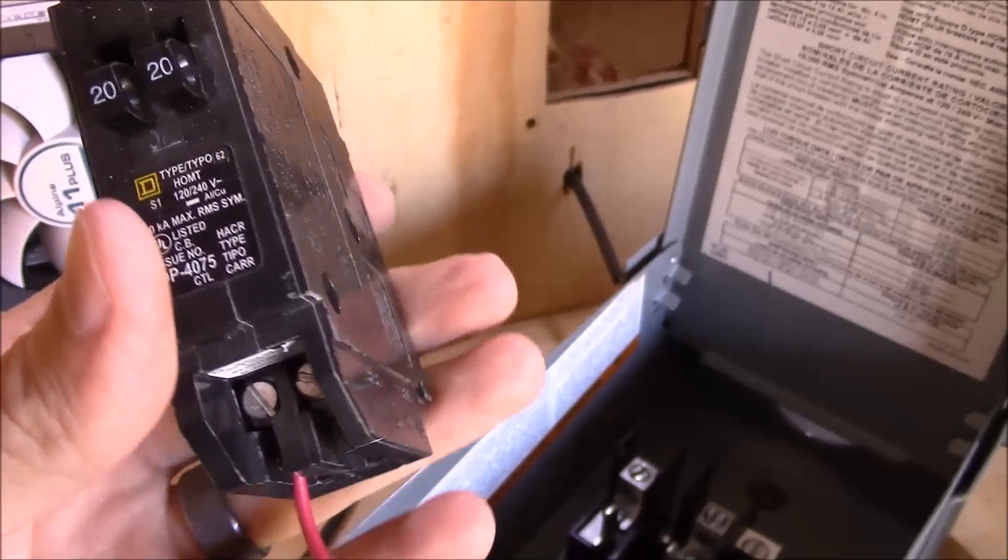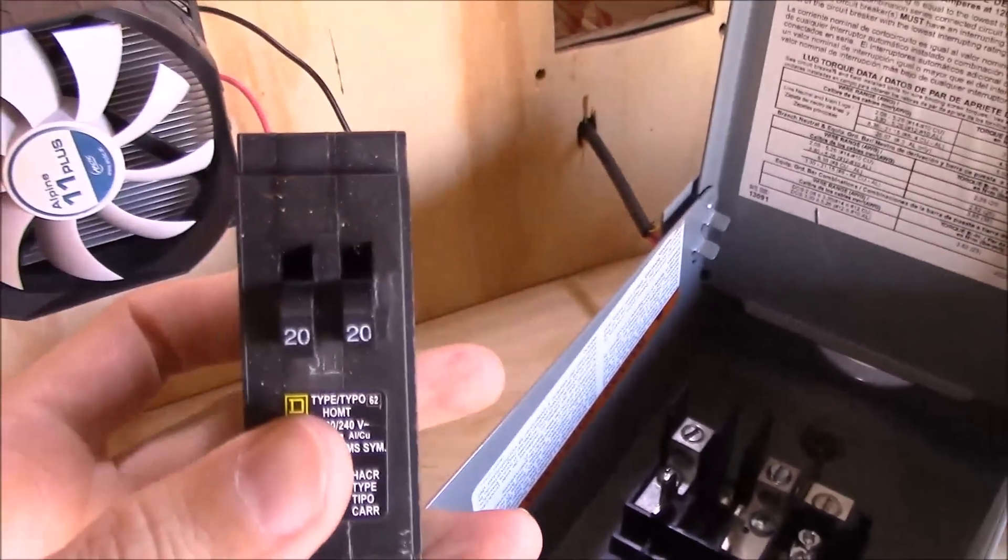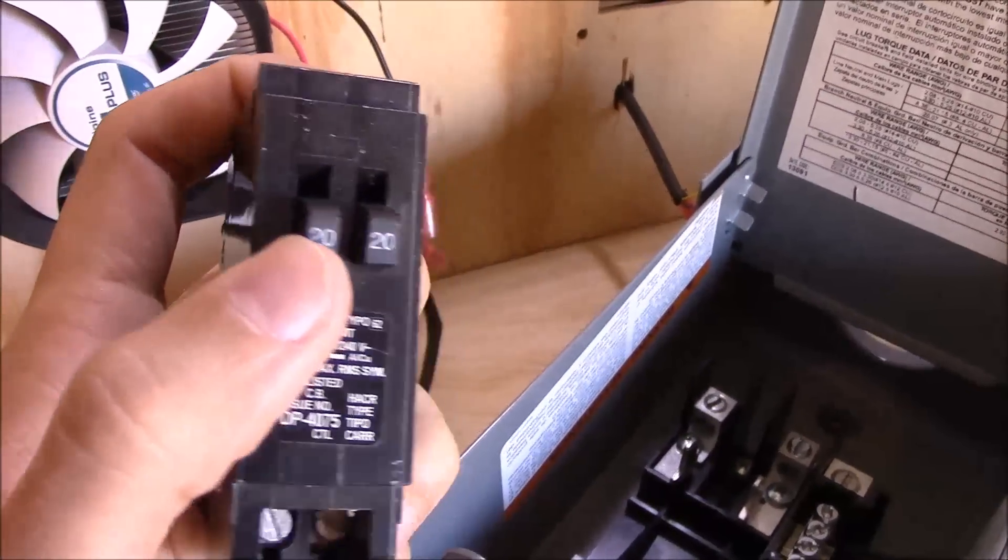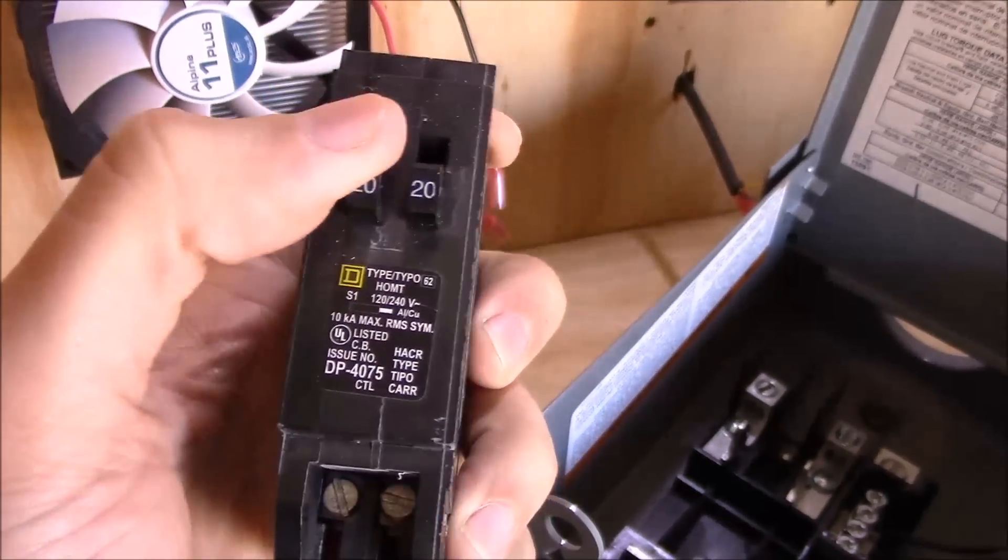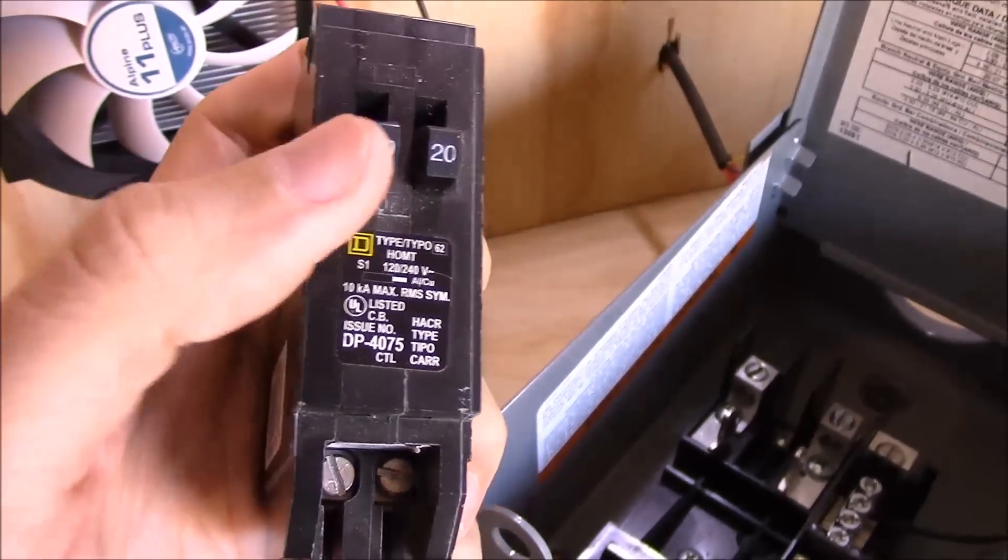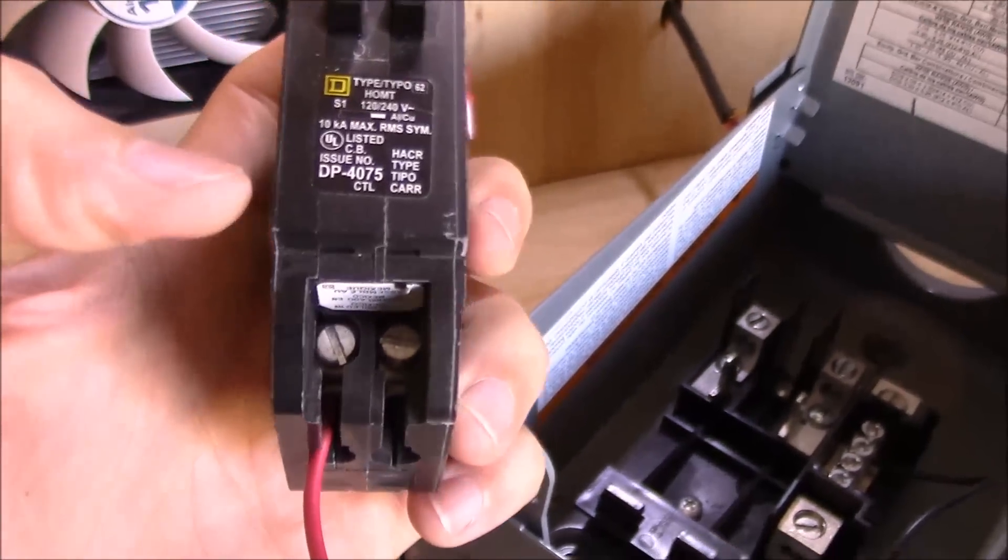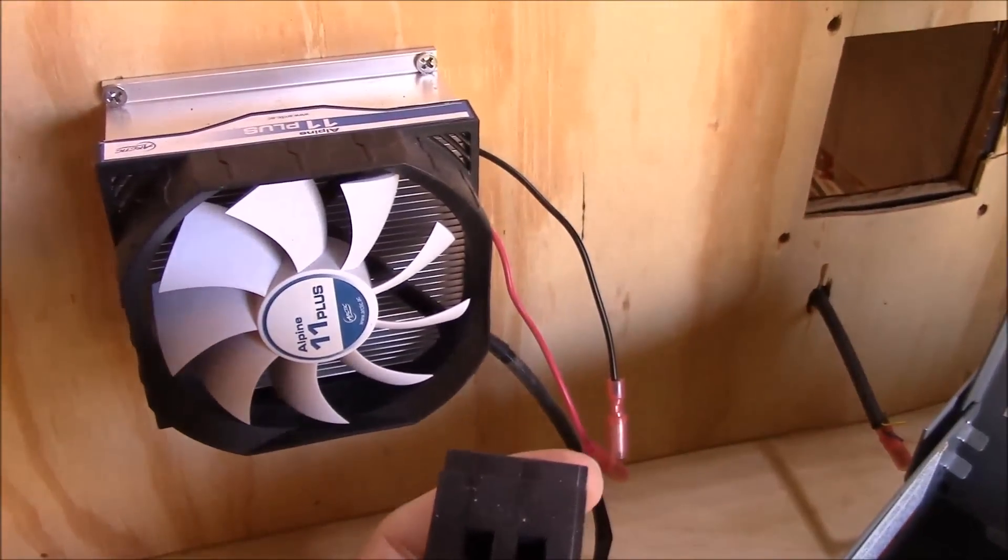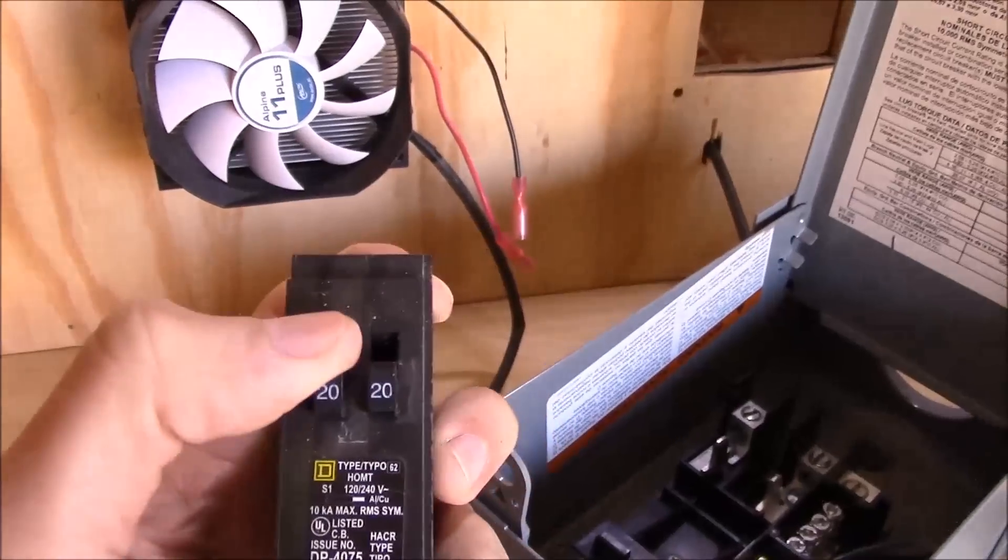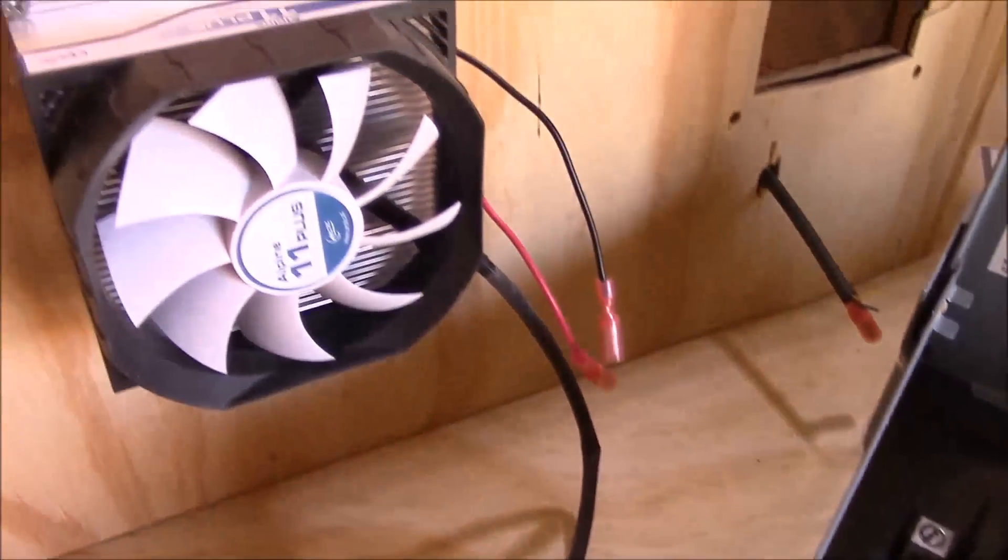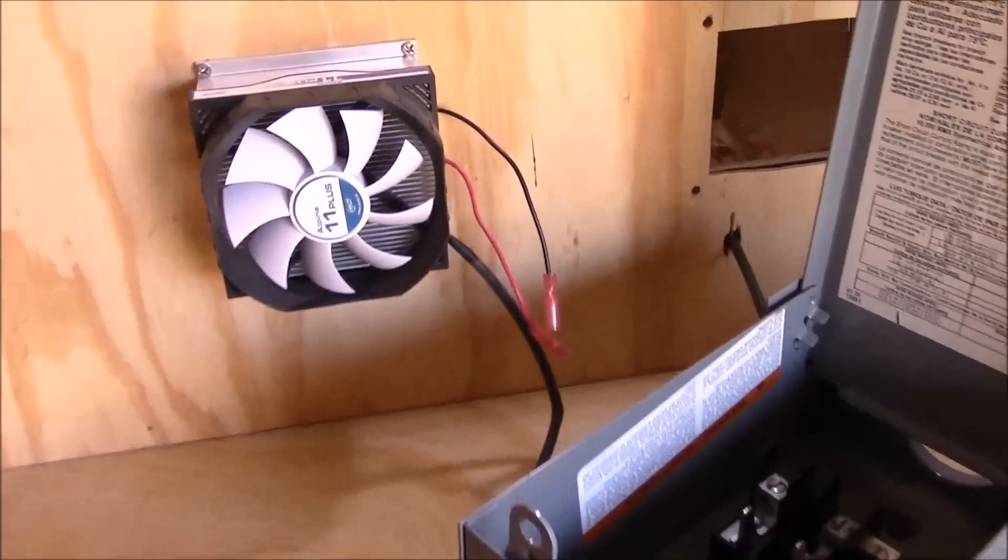Now, the reason I like to use a breaker or load center and breakers is because it adds a level of safety. You have essentially an on off switch here. You can shut down the power very easily. It's also safe because this is a 20 amp. So if I accidentally draw more than 20 amps, if I have a short circuit somewhere, this is going to trip and it's going to protect my devices from damage.